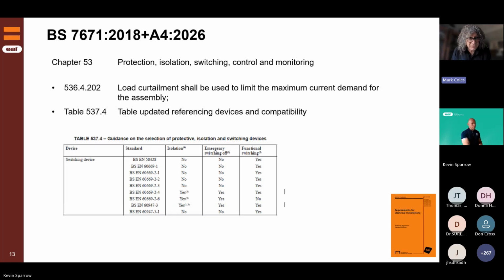Next one here is Table 537.4. Now this is the table about the types of devices that provide isolation and switching, also protective devices. So for instance, if you're looking for an isolator for something, remember that some devices are good to switch whilst current is flowing. Other devices are not suitable for that, and this table helps you with choosing the right device. This just highlights that a number of product standards have gone in to enable the procurement of the right kind of device for the installation that you're working on and the design. So I hope that helps.